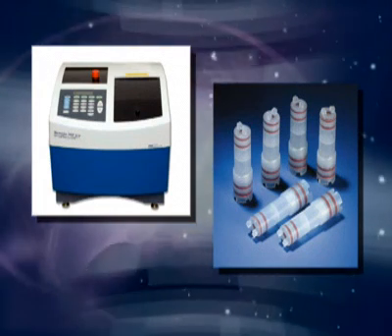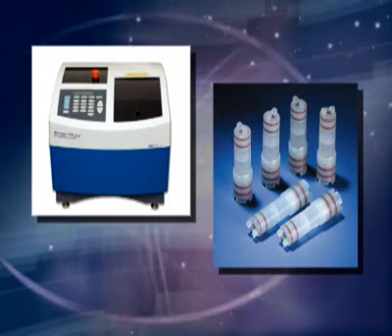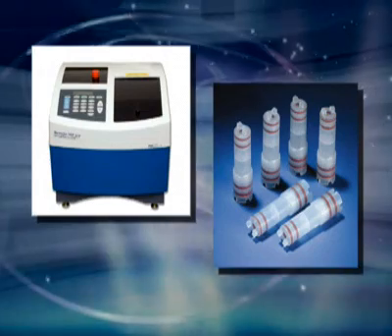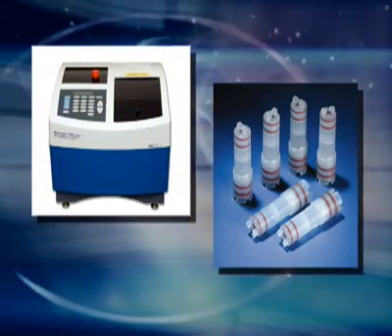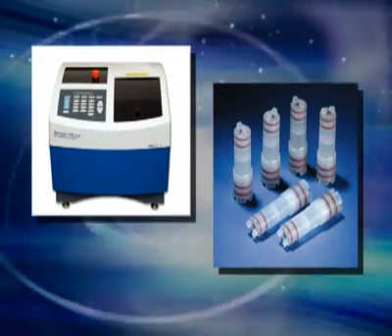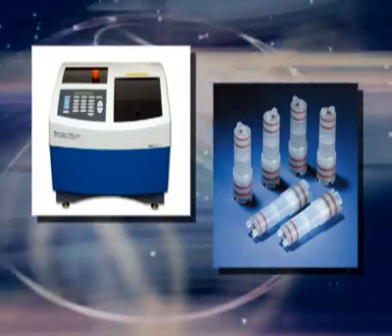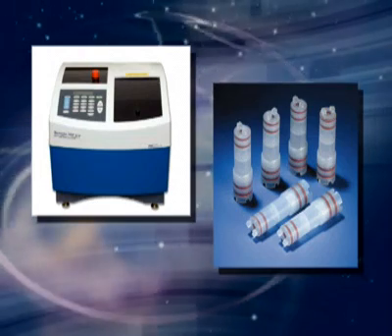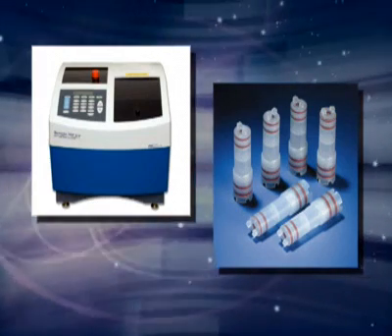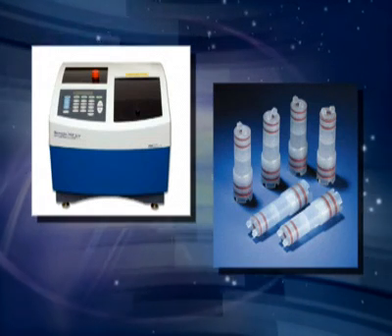The barocycler generates pressures from ambient to 35,000 psi and back to ambient in just a matter of seconds. Pressure levels, pressure times, and cycle numbers are controlled by a microprocessor. The barocycler reaction chamber can be temperature controlled, and the unique design of the PCT system reduces cross-contamination and risk of exposure to the user.